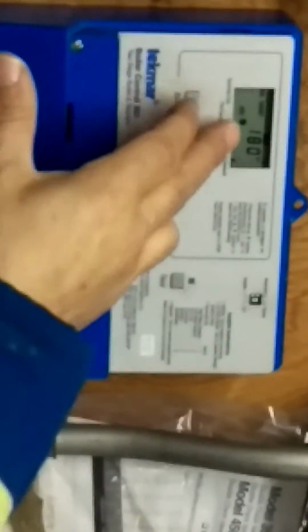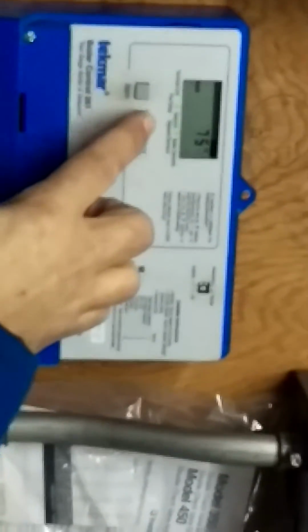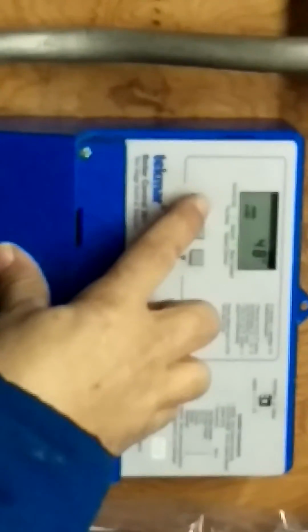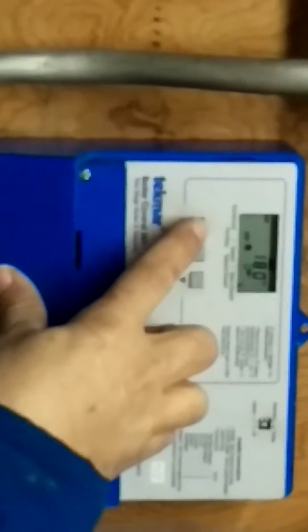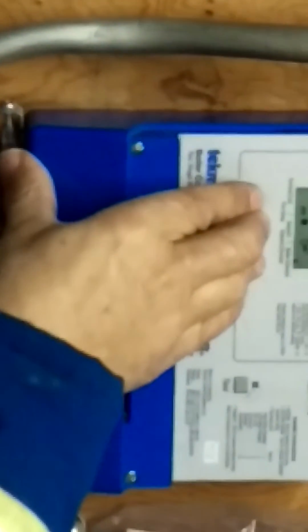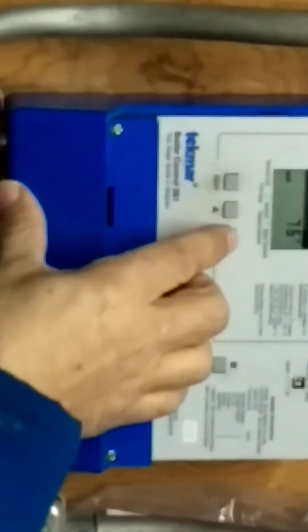Right now we've got a target of 180 based on our settings, and we've got the room set at 72. Perfect. So now watch what happens. I'm going to bring it up to 76. The boiler starts. It might have been ready to start anyway, just a fluke, but I'll show you how much difference it makes. Actually, it didn't change much right now. Oh, sorry, target is 185. By moving it 5 degrees, it told the target to go up 5 degrees higher on the room. So we're going to put that back at 72.